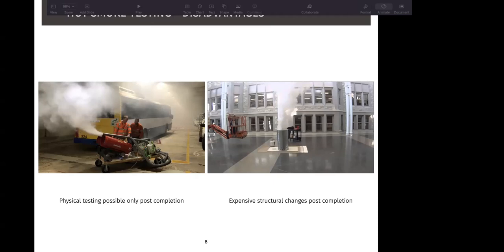So there were two problems with this case. One was that the testing could only be possible after completion of the building. If they had to bring in the smoke and do a physical testing, it would be post-completion. And the second would be that if there were any problems identified during this testing, then whatever changes were proposed would be an expensive structural change. So it would not be an easy change to conduct after the testing was complete.